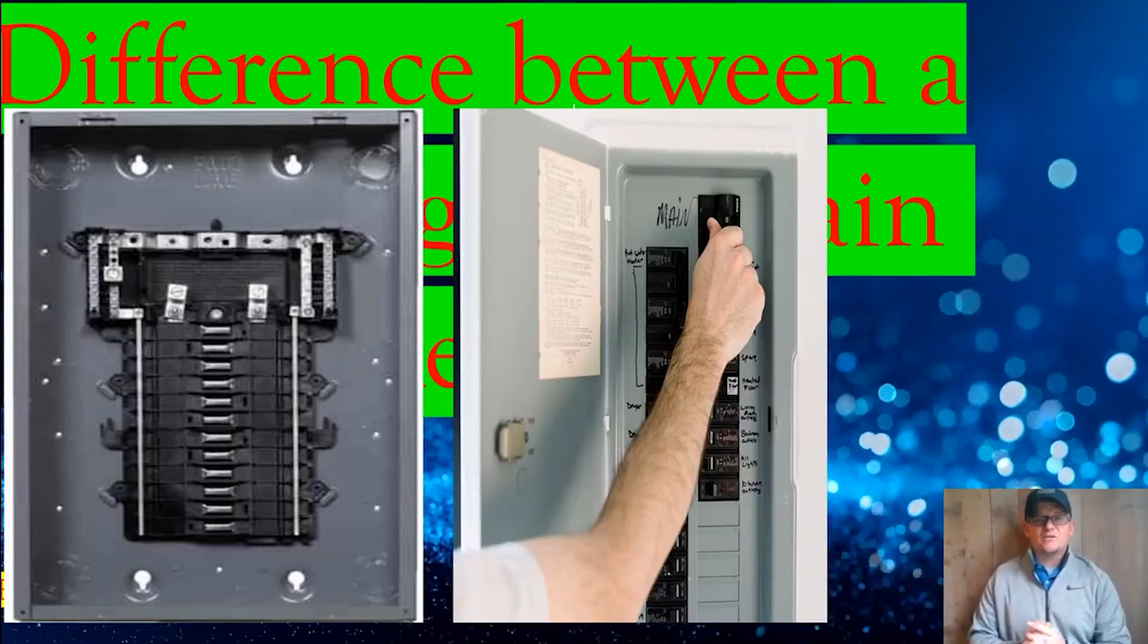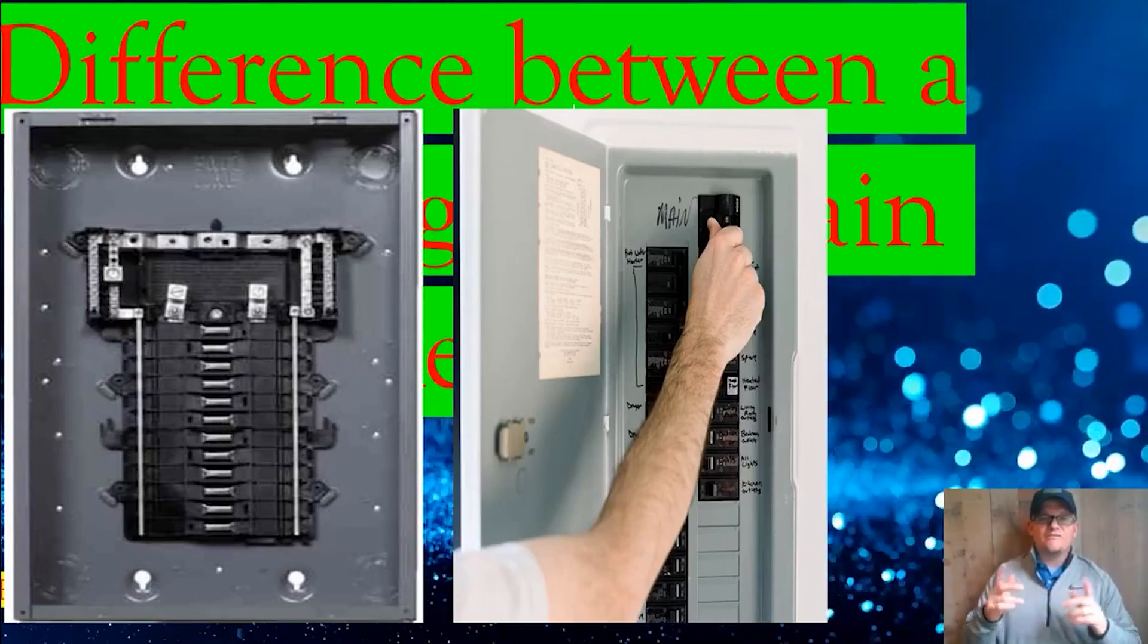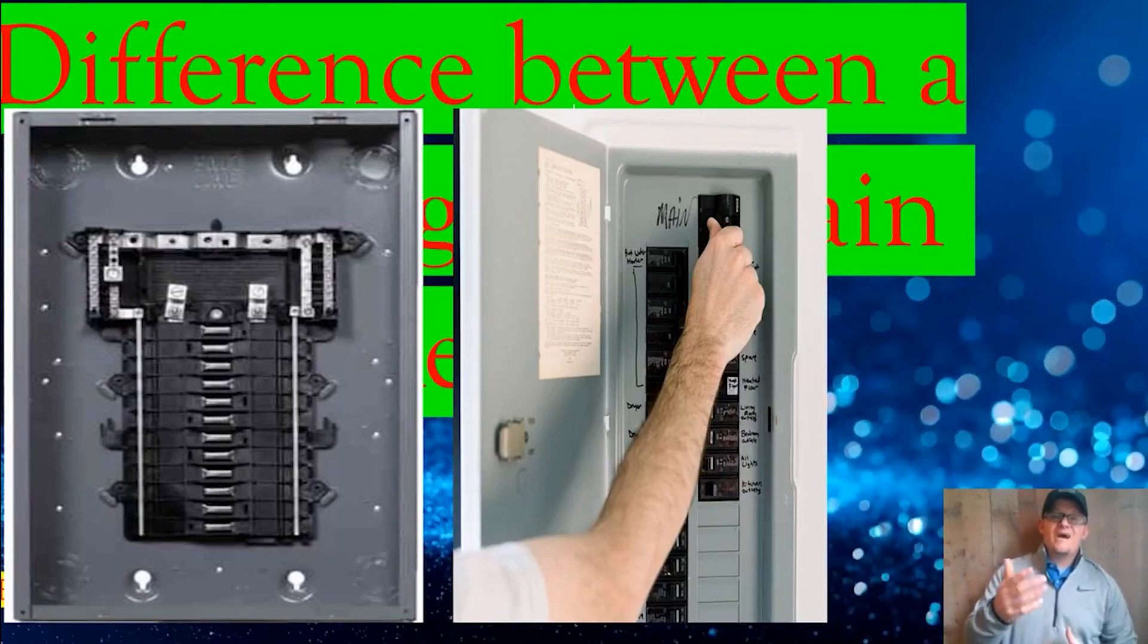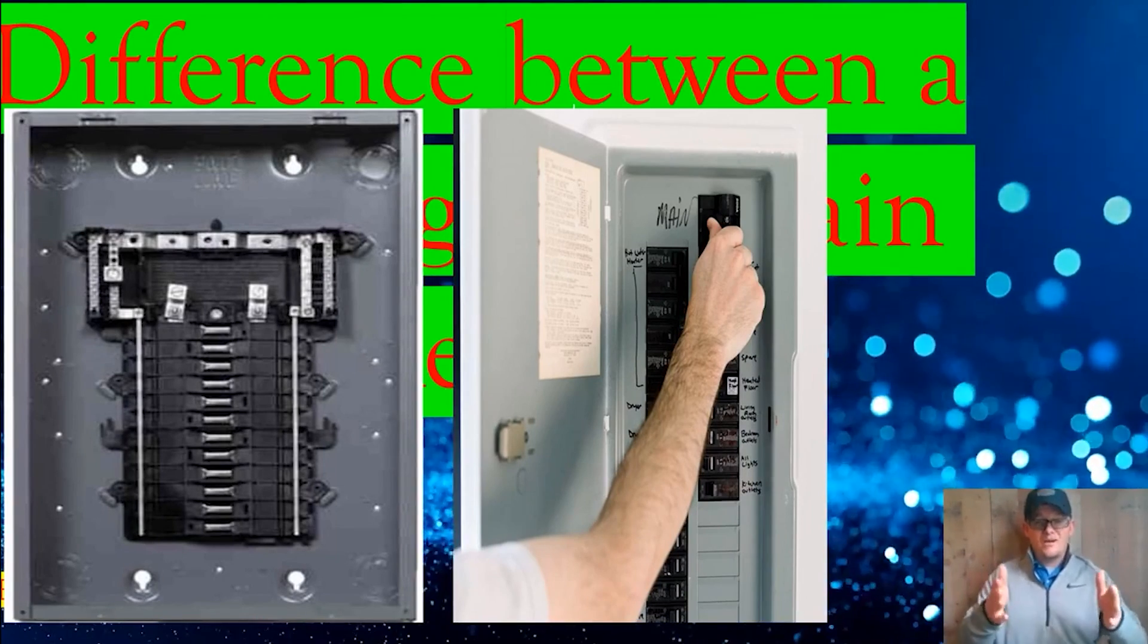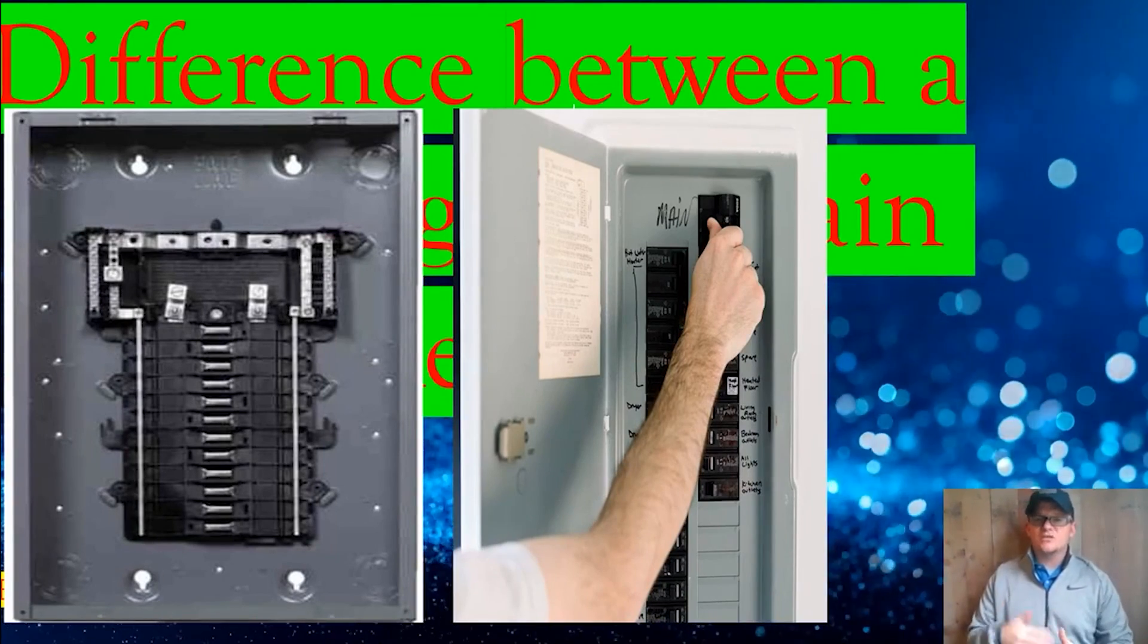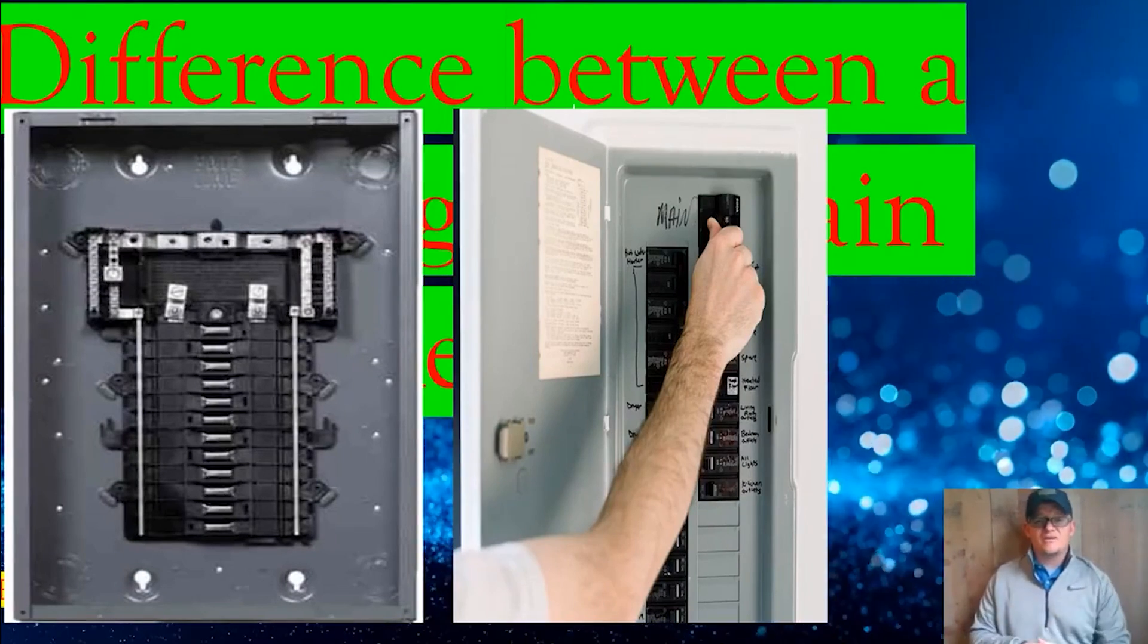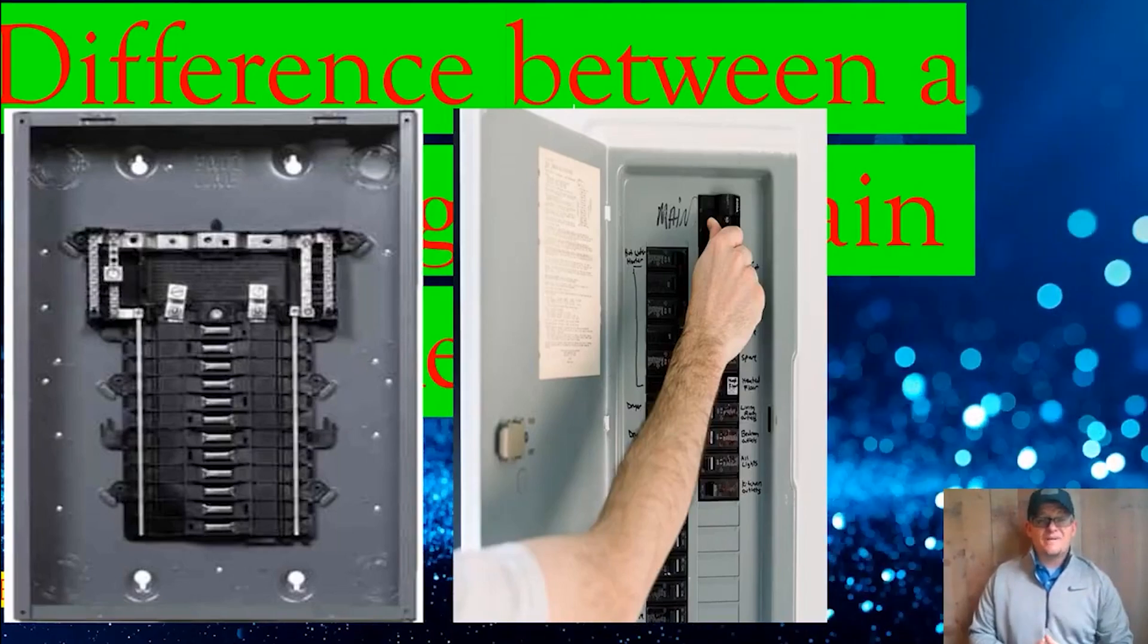You can legally have main lug panels. But every time you're at the first point of disconnect for that service, you're going to be required to have a breaker. And if your panel is the first point of disconnect in that service, like I've taught you about on this channel previously, then you're going to be required to have a main breaker.